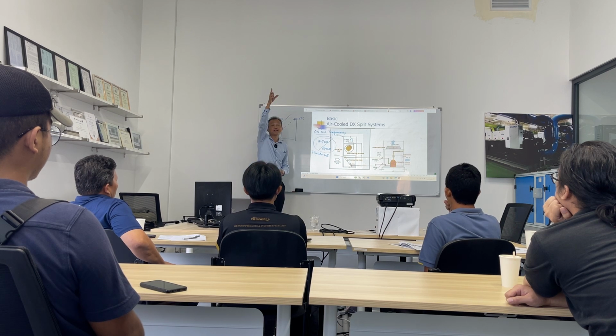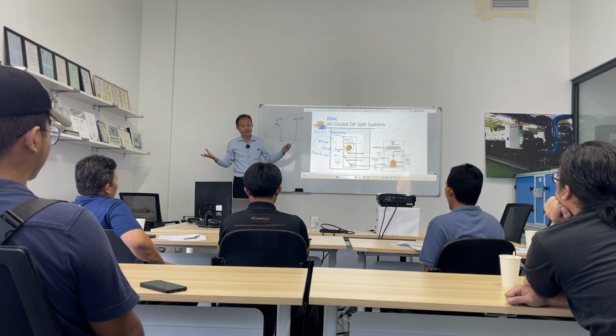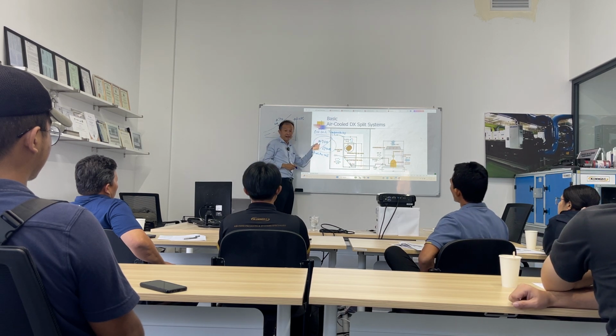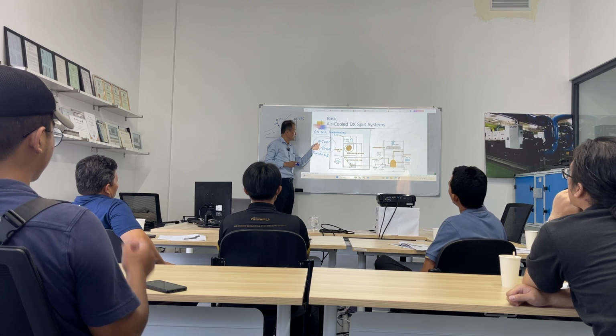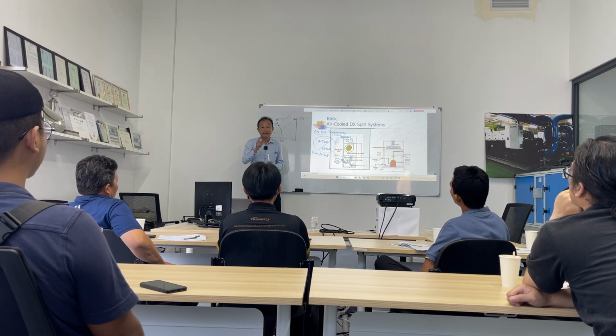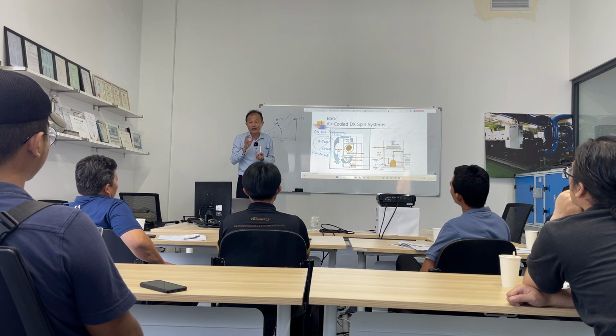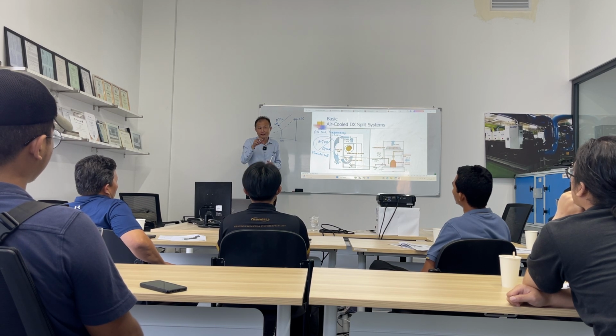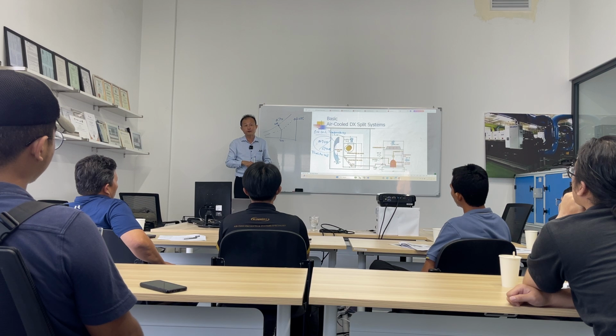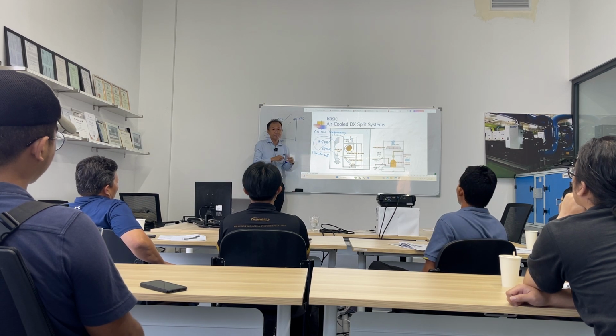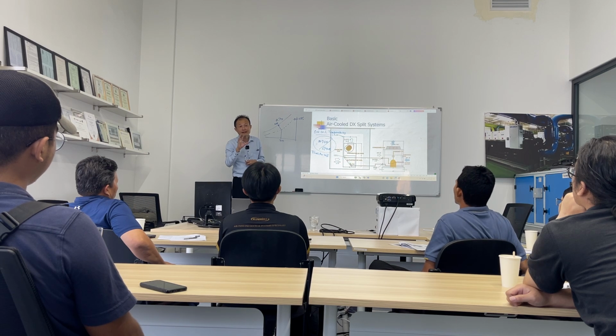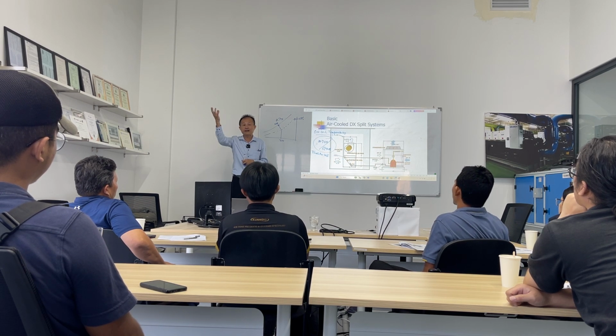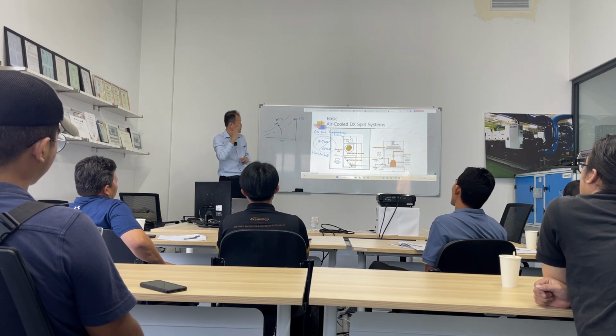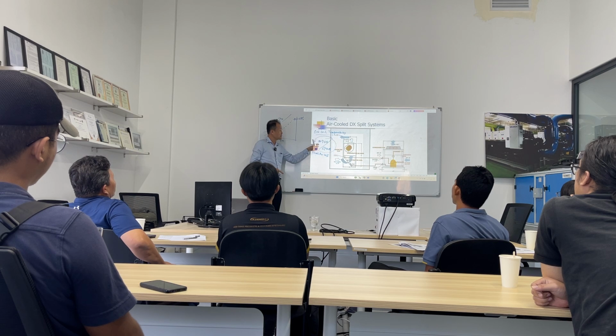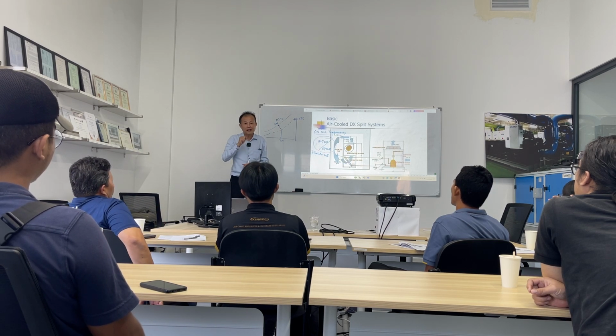Okay, but you know, all these designs do not come with fresh air, for example. So with this rating, please bear in mind, using higher on-coil temperatures gives a higher rated capacity in the catalog. So whatever capacity you select from the catalog, you have to be careful. That means the capacity might have been overrated by more than 10%, maybe 10 to 15%. So when you design any system, if you know that you are not actually using this on-coil condition, you had better mark up the capacity.